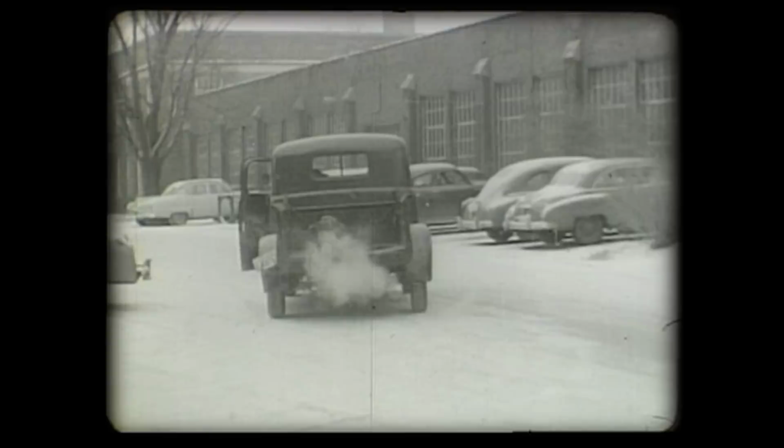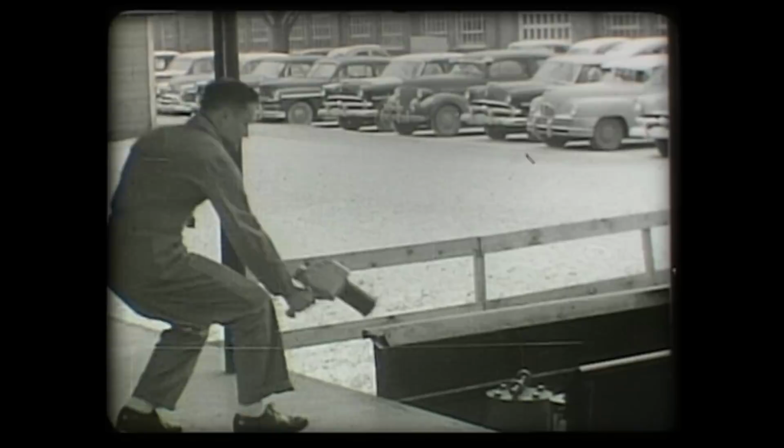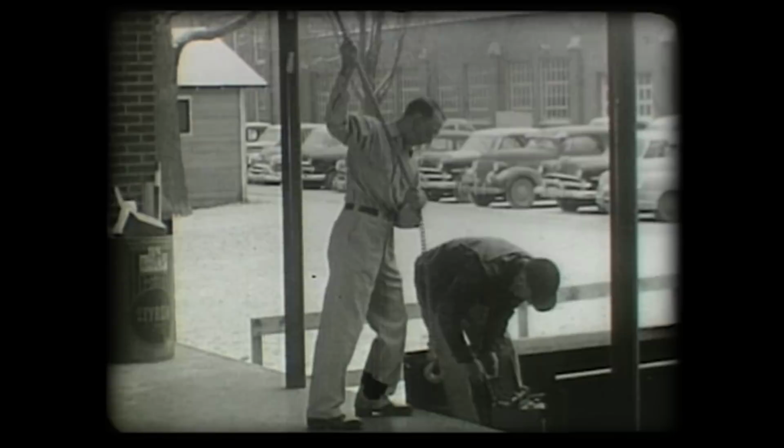The containers, or caskets as they're commonly called, are made of two pieces, bolted together, which eliminates the danger of harmful gamma radiation from the sample. A small aluminum thimble in the center of the lead cylinder serves as a case for the radioactive sample. The procedure for handling the radioactive or hot samples is set up by the Health Physics Department under Milo Voss here at Iowa State. And each time the casket is moved, it is checked to see if any leaks have developed.